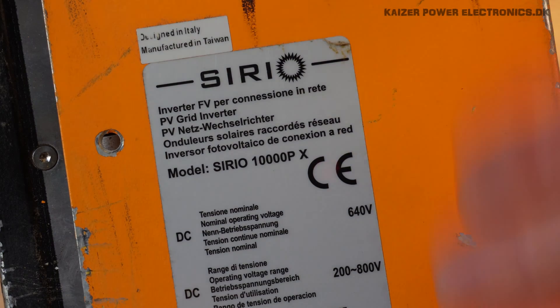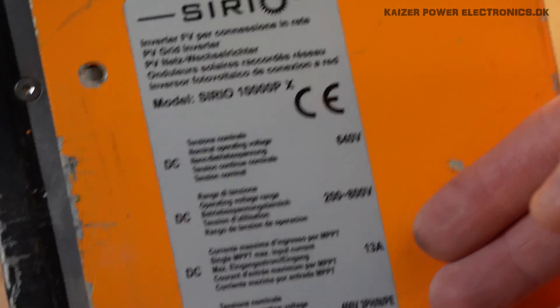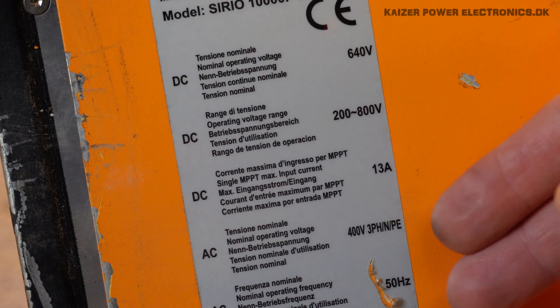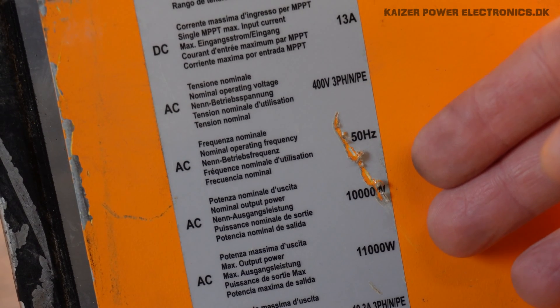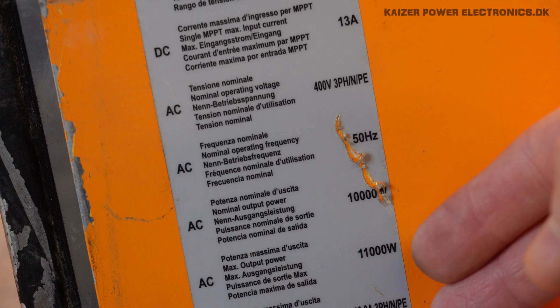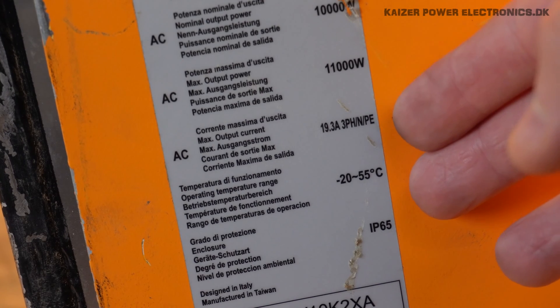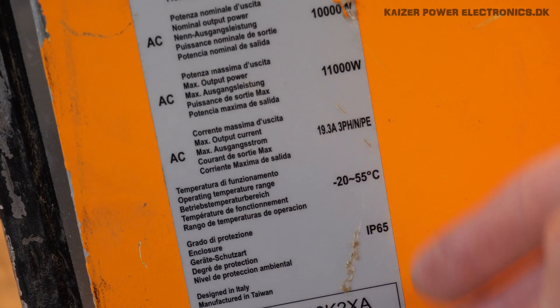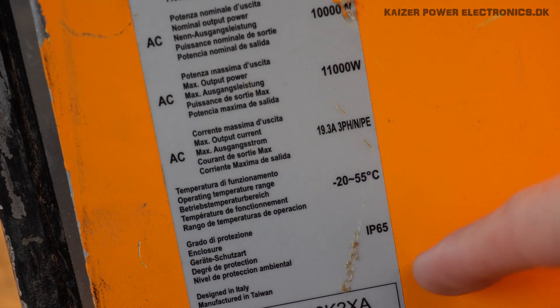The Sirio 10000P specifications: it's rated for a 640V DC solar panel voltage, but can use between 200 to 800V, and a 13A string input current. It is made for a 3-phase connection, with a 10,000W nominal load, and it can do a peak of 11kW. That corresponds to 19.3A 3-phase AC, rated for minus 20 to 55 degrees Celsius surrounding temperature. It's IP65, meant for being installed outdoors.